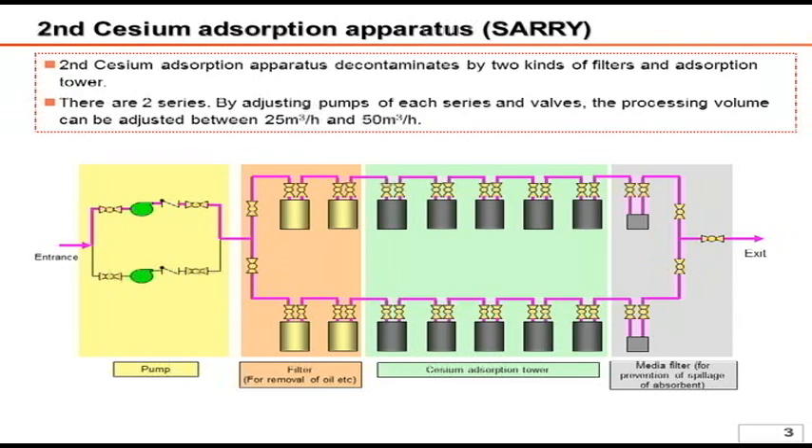Like Kurion's system, SARRY has two vessels in line which remove oil and impurities. Next, four vessels out of five absorb cesium. Lastly, the media filter — a small filter — processes the water in order to prevent absorbent leakage.